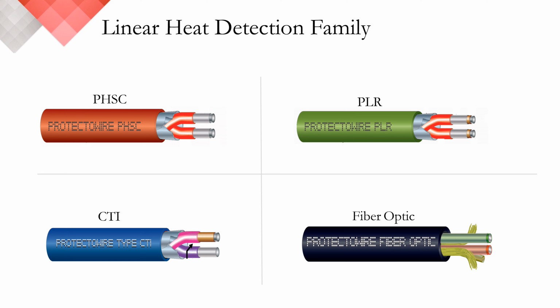And lastly, we have fiber optic, which is widely viewed as the next generation in linear heat detection. Standard digital linear heat detection is considered a passive device, meaning that it sits in a ready state waiting for the fixed temperature to be achieved before activating. Fiber technology, on the other hand, is an active system that reports real-time temperature profiles anywhere along its length up to 10 kilometers. That's a little over 32,000 linear feet off a single fiber, and then can be further segmented or zoned into 256 unique partitions anywhere along its length, which is all done through software.